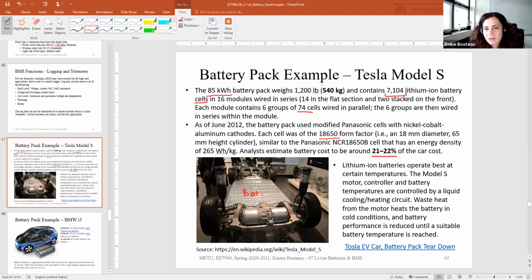If we know the number of cells and their ampere-hour rating, we can calculate the kilowatt hours of the battery pack, but we also need the voltage. When we talk about a cell's charge capacity, we usually give ampere-hour values, which we then multiply by the voltage. Since knowing the cell chemistry tells us the voltage, capacity is usually given just in ampere hours. So here we can calculate the ampere hours: 7,104 cells and 85 kilowatt hours.